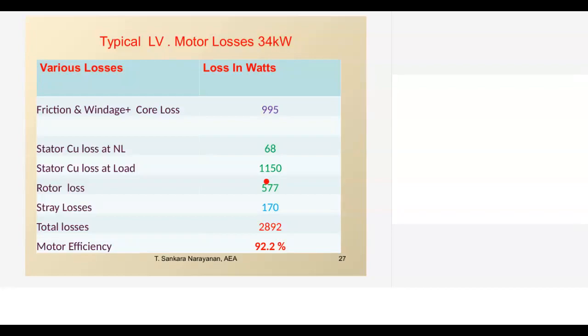On the rotor side, mostly the rotor is an aluminum die cast rotor. If the rotor has a problem, if a rotor bar has opened, then it will be rectified again. So rotor loss increase may not predominantly occur because of rewinding. There is a marginal increase in resistance loss and a major increase in the no load loss. This is why, as a good industry practice, you always measure the no load current and no load loss for the new motor. This can be compared whenever the motor goes for rewinding, and then it can be reviewed. Second thing, if the rotor is damaged, there can be an air gap issue. If the air gap is increased, then definitely PF will also change.